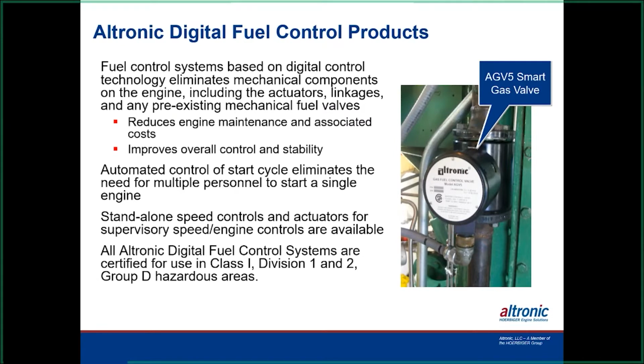And the one that's shown is the AGV5 valve. That's a valve all by itself. It has no controls to it. It reads pressures, but to control the valve, you need another source, either a PLC or another type of controller. So we'll get into a little more of that later.